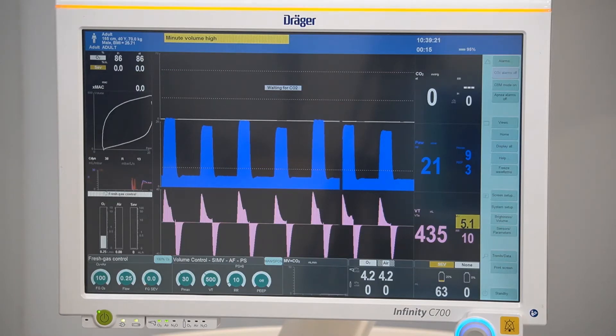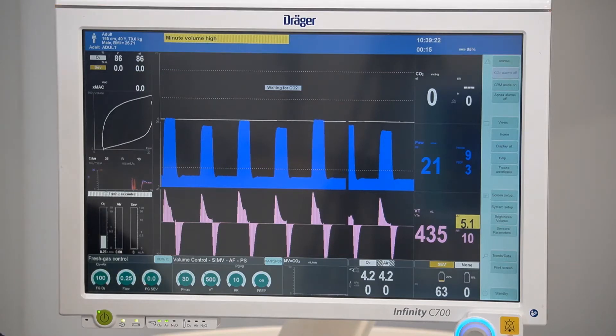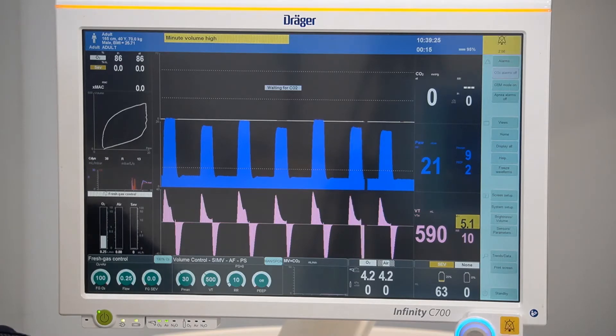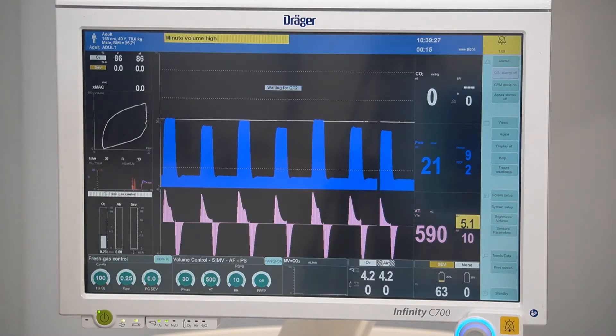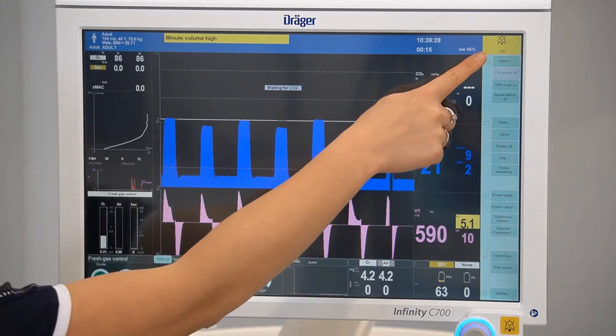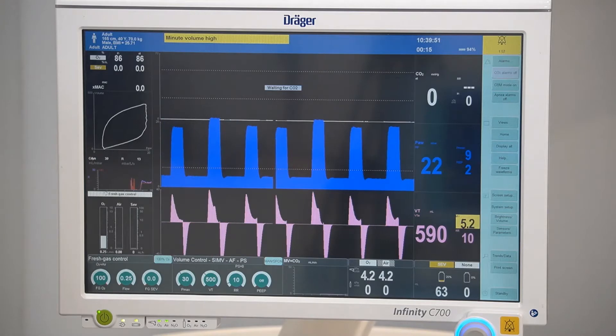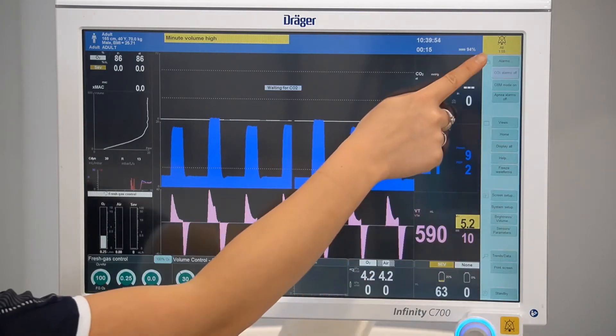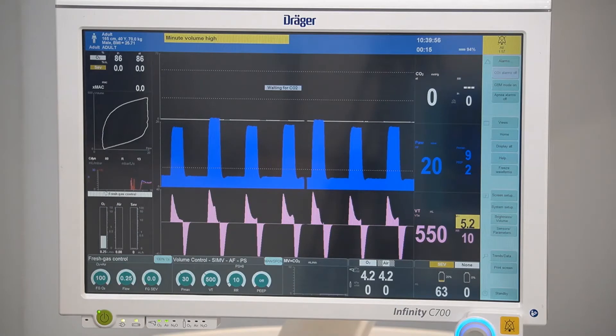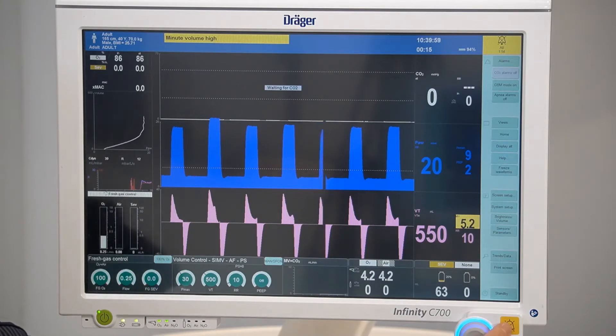To silence an alarm, the soft key for audio silence can be pressed. This will silence the alarm for two minutes, with the remaining time displayed in the top right-hand corner of the screen. Pressing this button a second time will silence all audio alarms, and pressing it again will cancel the audio silence function.